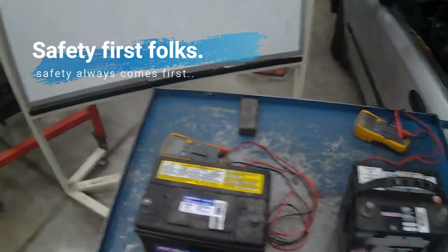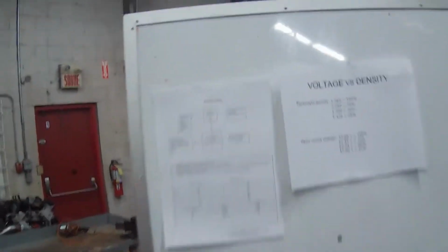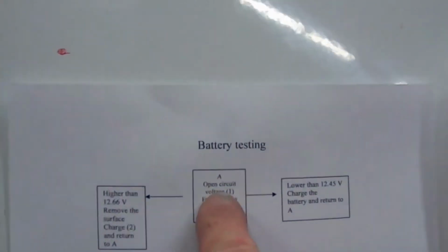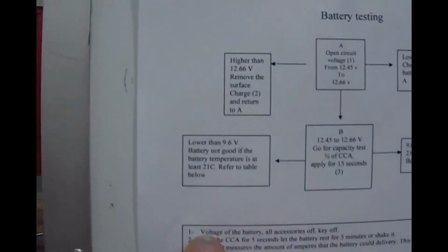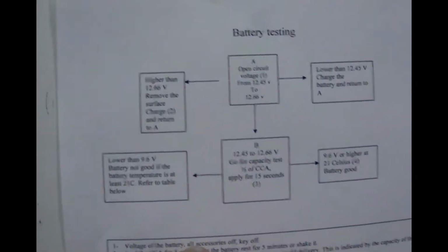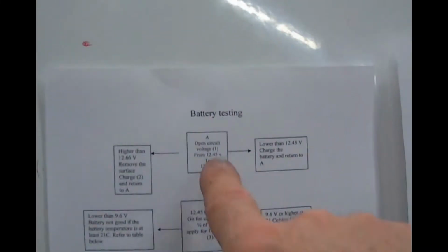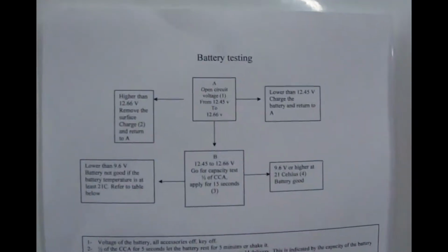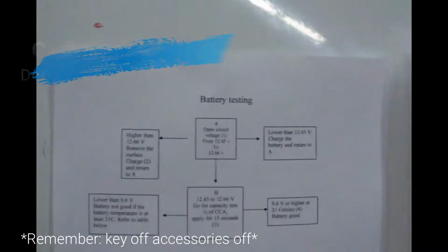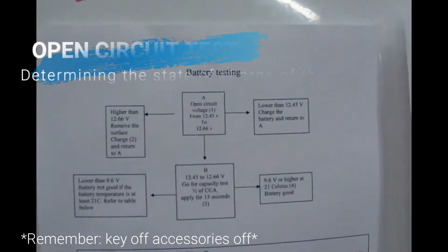Second, I want to see what I should do with this, so I'll look at the chart here. It says the first thing to do is evaluate the open circuit voltage. Open circuit voltage tells me the voltage of the battery with all accessories off and key off. It simply tells me the state of charge. The capacity test, if I can do that, will tell me if the battery is good or not.